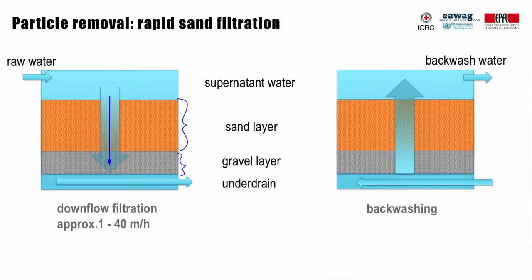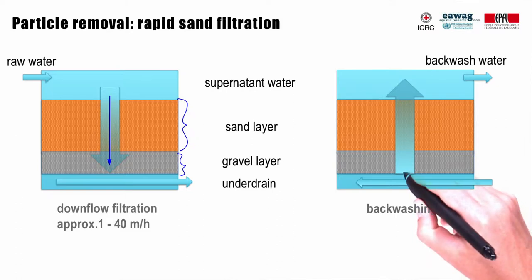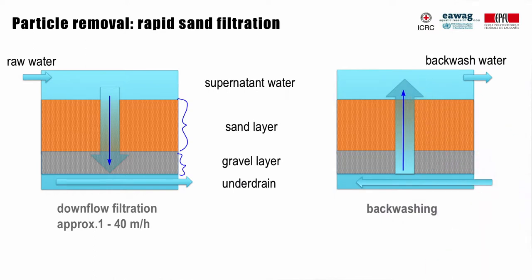After trapped material accumulates in the first layers, the filter requires backwashing — a reverse flow of water to remove accumulated material. The filters are operated at a linear velocity of 1 to 40 meters per hour, which is considerably higher than in slow sand filters, which we discuss later.